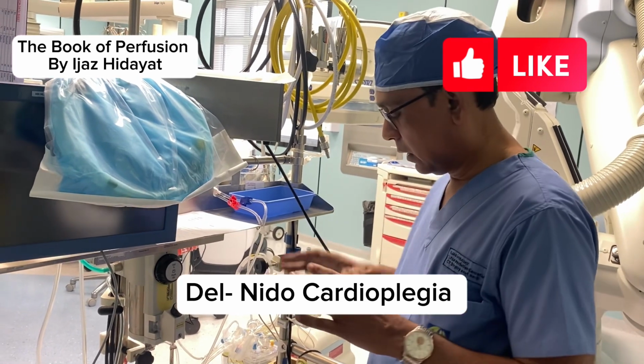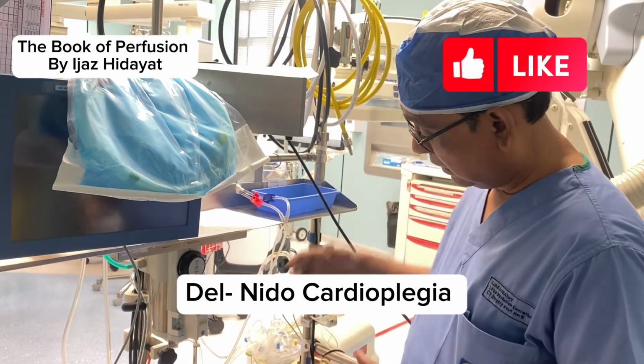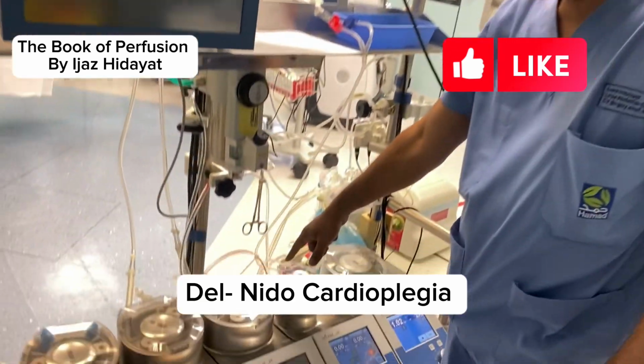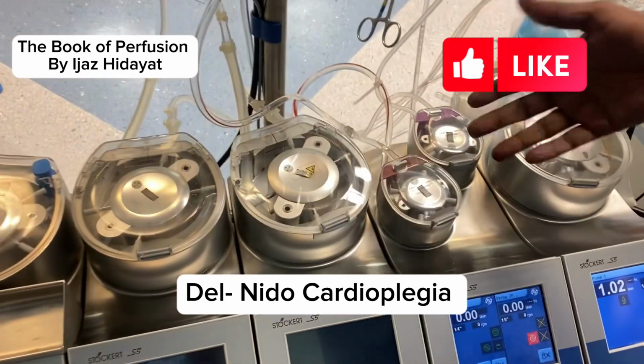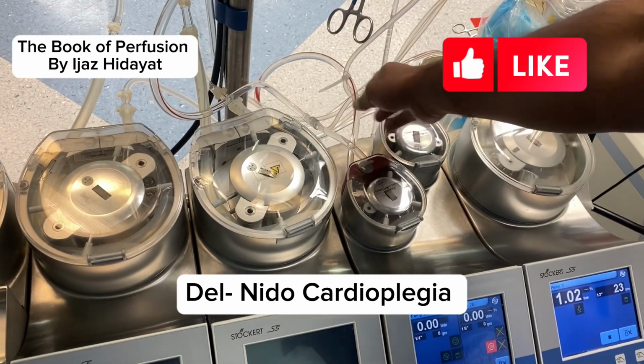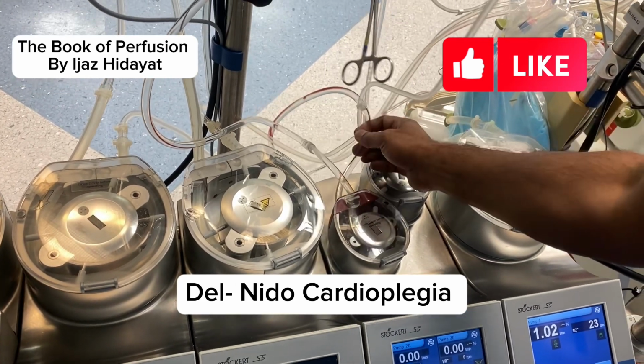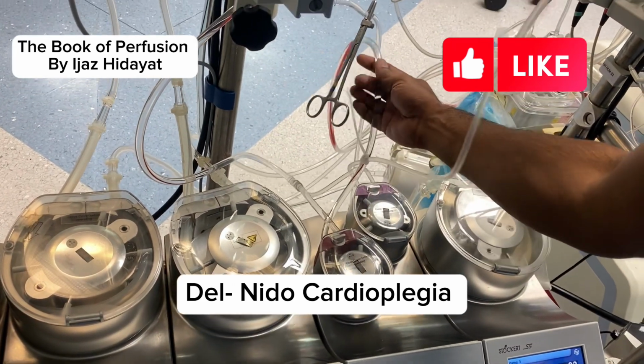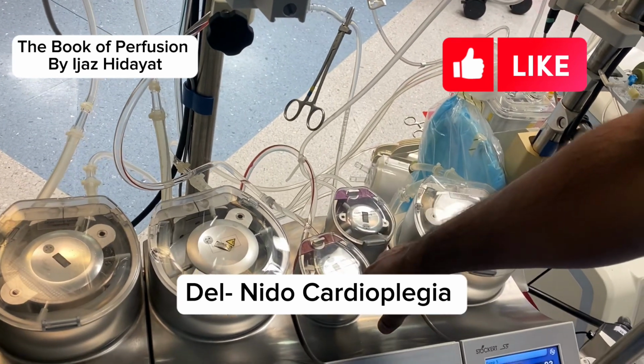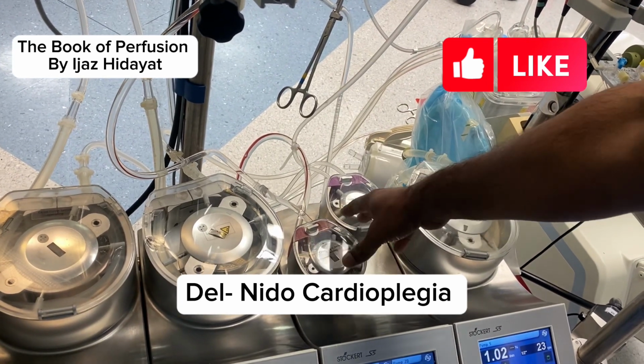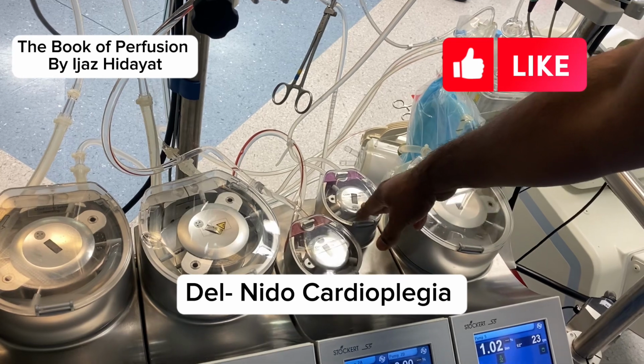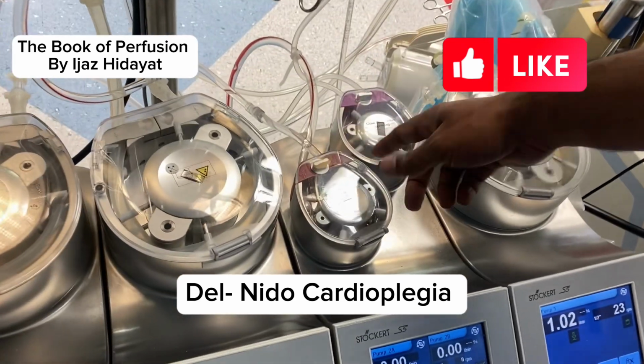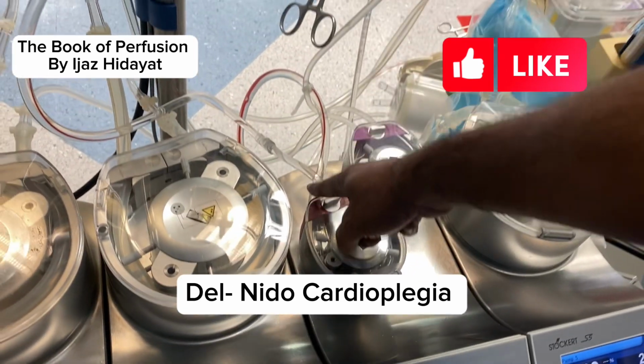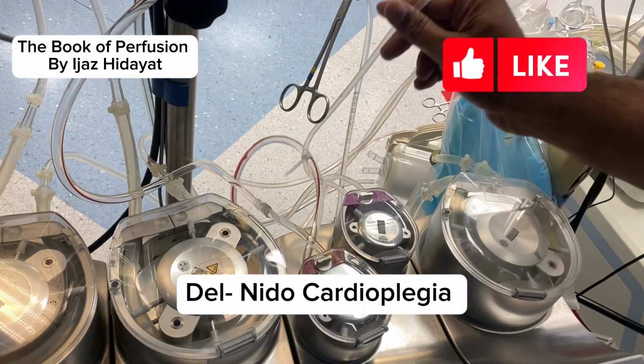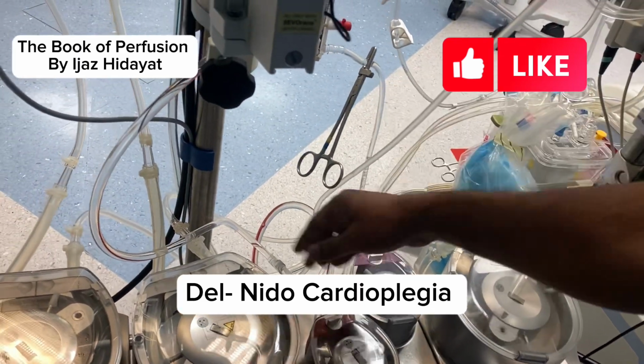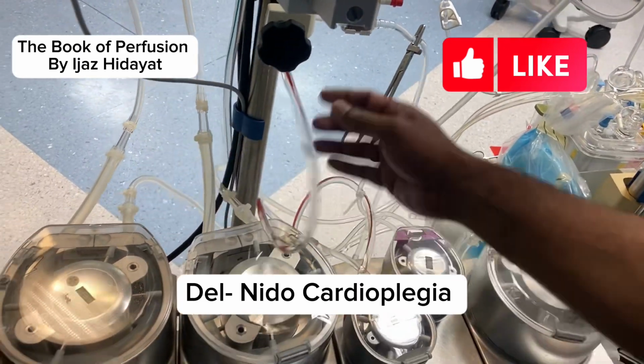In the Del Nido cardioplegia, see, this is your routine blood cardioplegia circuit. We are getting the blood from the oxygenator into the main pump. This is a dual pump, so this is the master and this is the slave. This is the routine one I'm showing, where we get blood from the oxygenator and crystalloid, mix them here, and return them into the cardioplegia.